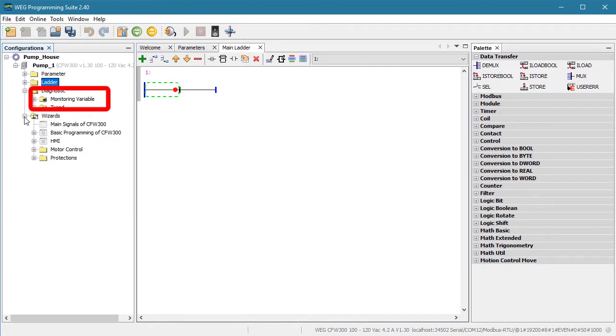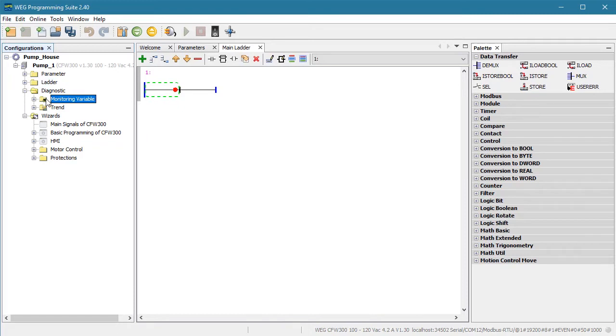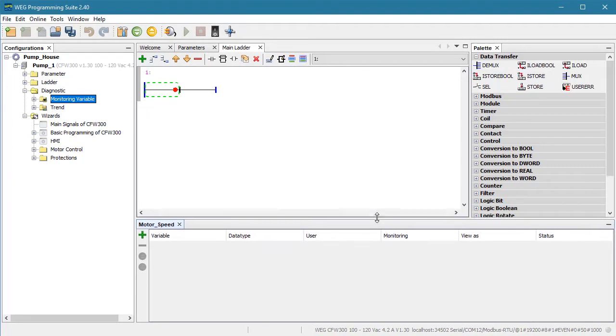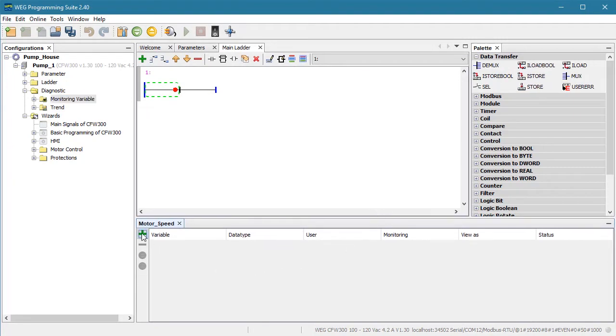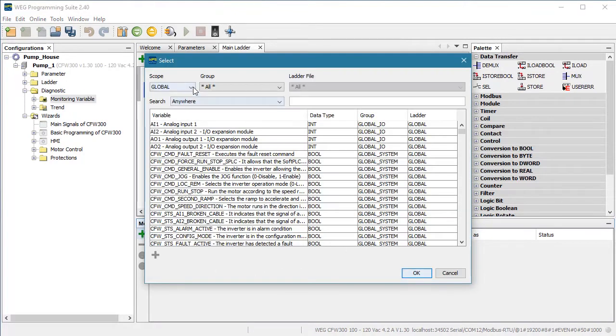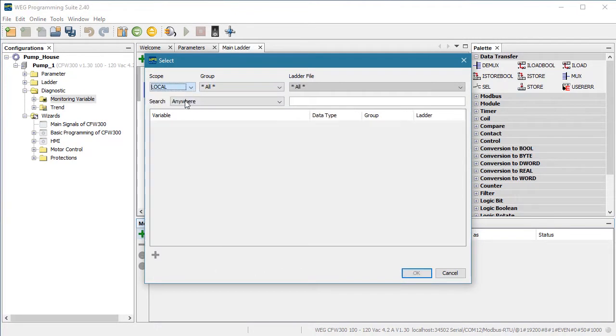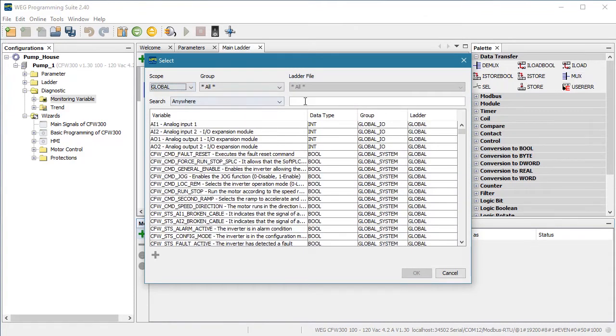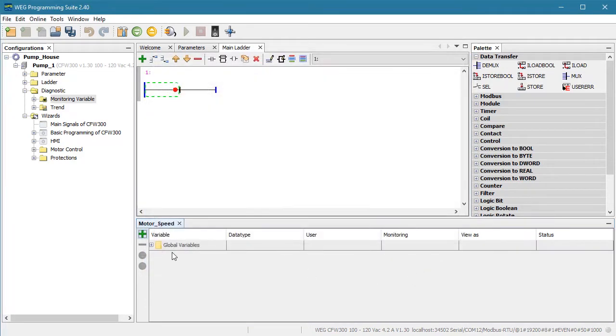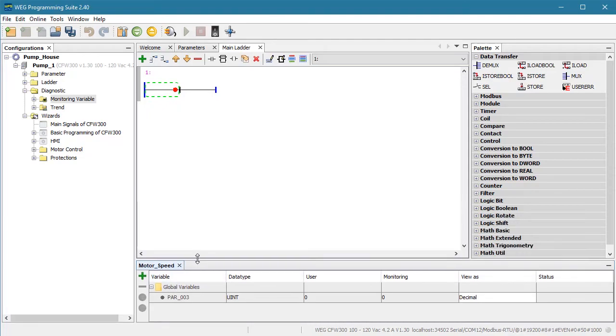With this monitoring variable diagnostic, we can create a custom table of variables we want to monitor. They can be parameters, system variables or soft PLC variables – any variable in the entire resource. Right click, give it a name and look – our new variable monitoring table appears down here. You can then add global or local variables. If local, then you can actually select which ladder file to pull them from. And you can search, which is a super easy way to find variables. We will use this a lot in the soft PLC videos. For now, just be aware that you have this powerful tool available to you.